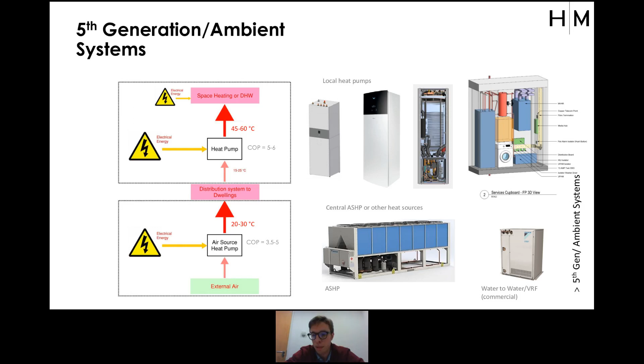The other great consideration is often with these high-density resi schemes, you've got commercial to some degree, retail units on the ground floor or amenity space that you can harvest some heat from. So whether that be a water or VRF system integrated into this system, it's a great story, because that will offset your central plant running and improve your overall efficiency and carbon emissions. So that's a really interesting point.